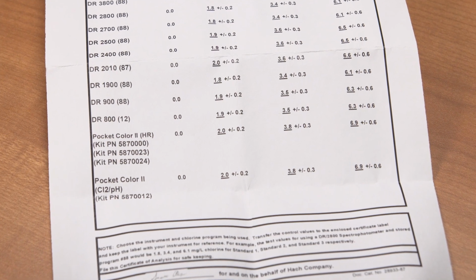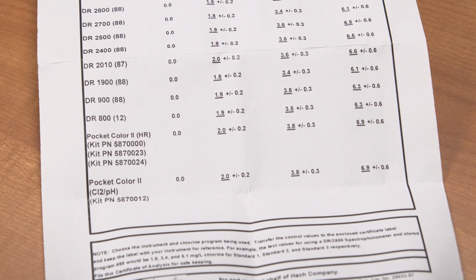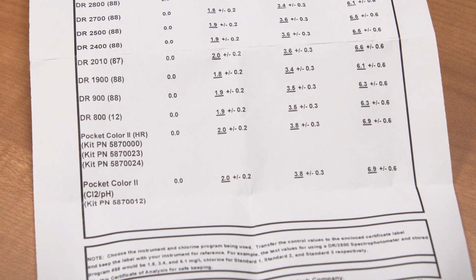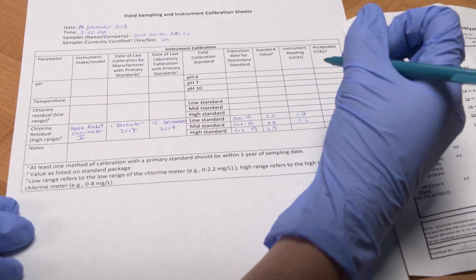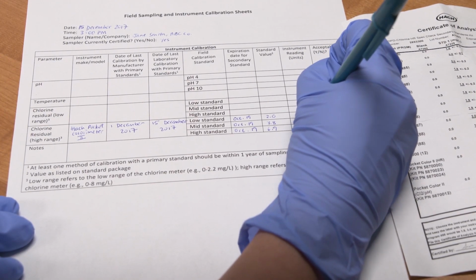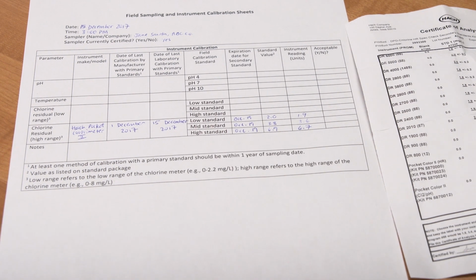If the readings are not within the correct range, we will discuss how to troubleshoot your instrument at the end of this video. You will want to keep records of performing the secondary verification, which could include the date performed, measurements of the standards, instrument used, standard product number, and expiration date.